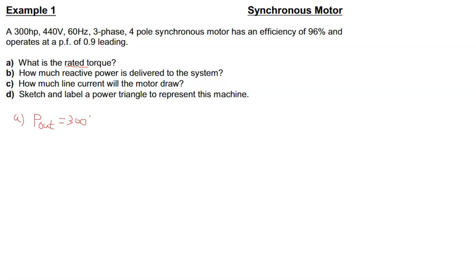And it's 300 horsepower. And we want to convert that to watts before we put numbers in the torque formula. So 746 watts per horsepower. And that gives P out at 223.8 kilowatts.